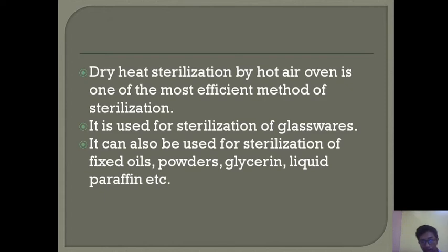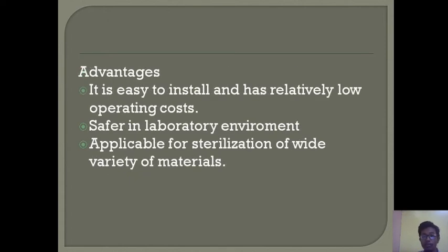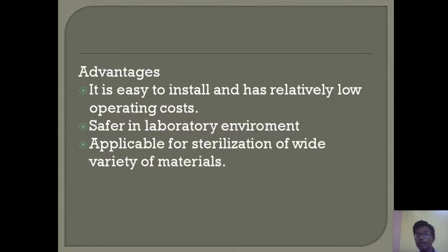Some advantages of dry heat sterilization by hot air oven are: it can be easily installed and has a relatively low operating cost. It is safer in a laboratory environment than moisture sterilization by autoclave, because an autoclave is a pressurized chamber, so the hot air oven is safer. It is also applicable for sterilization of a wide variety of materials.